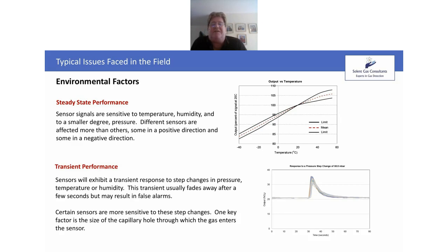So you have a steady state performance and transient performance. For steady state performance, pressure is minimal, temperature and humidity more so. You can see on the graph at the top there, this is an example of temperature response. You see it's normalized at 100% at 20 degrees C. As the temperature increases, you can see that typically the sensor signal will also increase. The transient performance, again, spikes or step changes in temperature, humidity, or pressure will result in these transients. That will result in a likely false alarm.